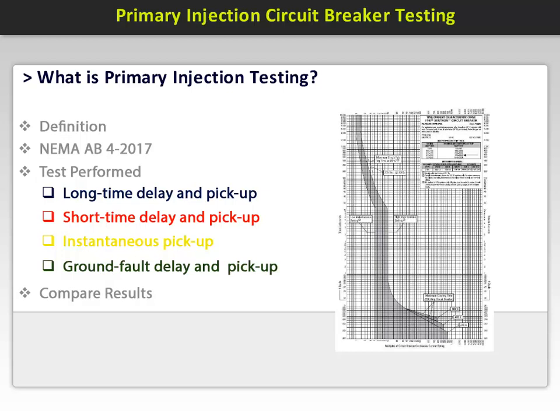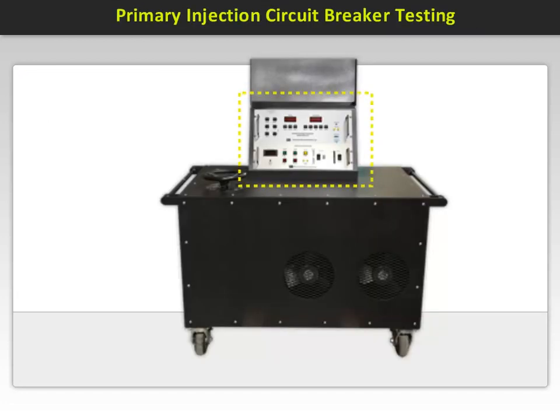Many manufacturers of primary injection test kits include most manufacturers' trip curves in the software. The heart of the test set consists of a microprocessor core unit connected to a motherboard which contains a regulated power supply and some support circuitry. Software contained in the microprocessor performs the required real-time data collection, measurement, user interface, and output control functions.